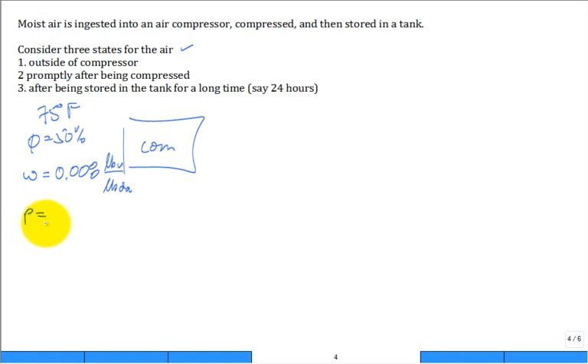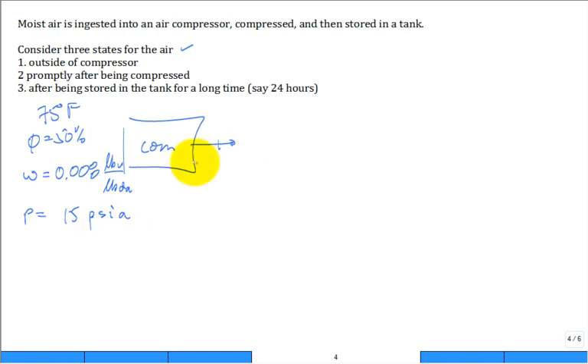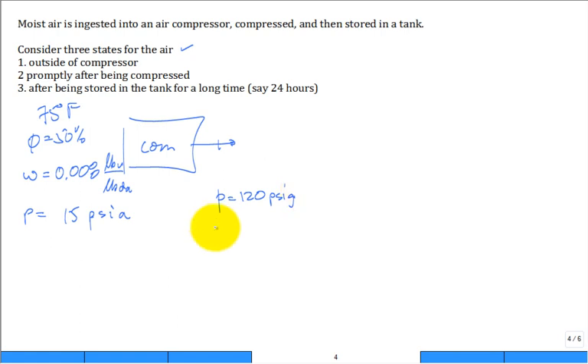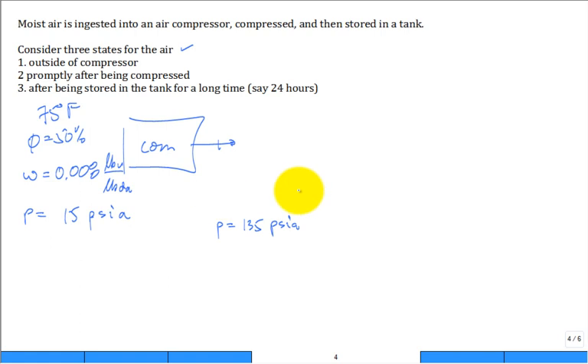The pressure of the air in the room before ingestion is roughly 14.7 — round off to 15 psia. What is the pressure coming out of the compressor? About 120 psig. That's gauge pressure, so we add 15 to convert to absolute: 120 + 15 = 135 psia. There's a little copper pipe that comes out of the compressor and dumps into the tank.